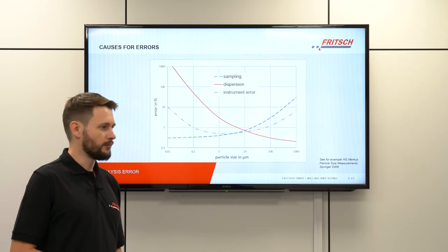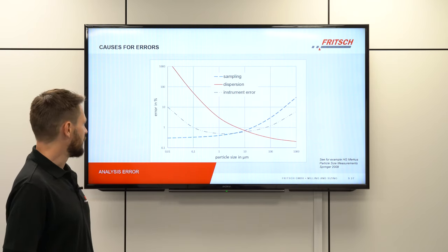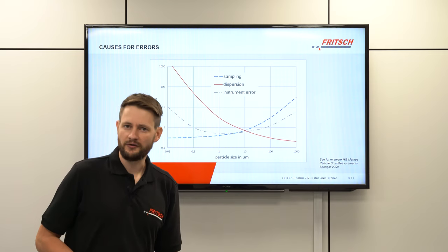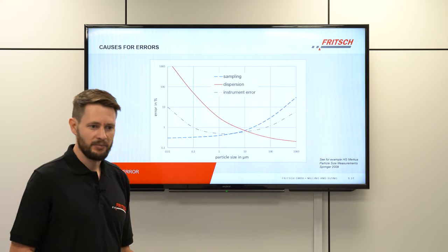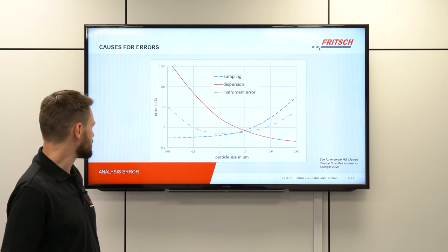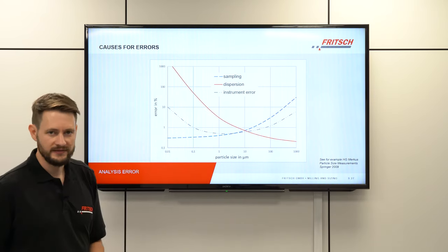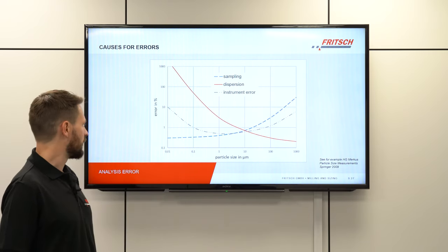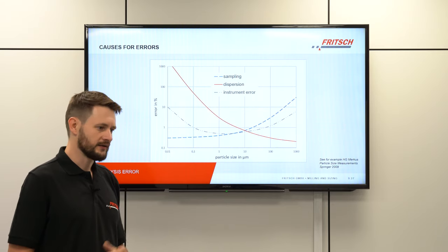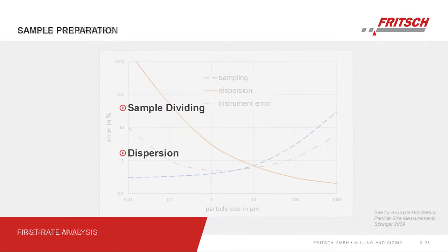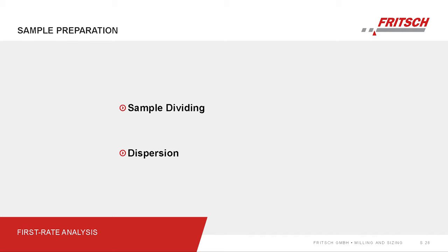Last but not least, there are instrument errors, which we cannot really influence as users. The minimum instrument error occurs around the range of 1 to 10 micrometers, due to the optical setup of the instruments — essentially physical reasons. To summarize: sample preparation basically consists of sample dividing and dispersion, which are the two main error sources in sample preparation.